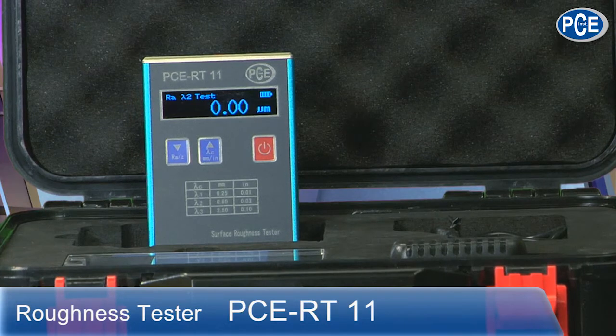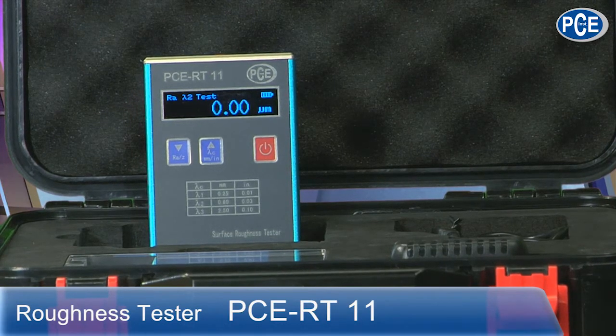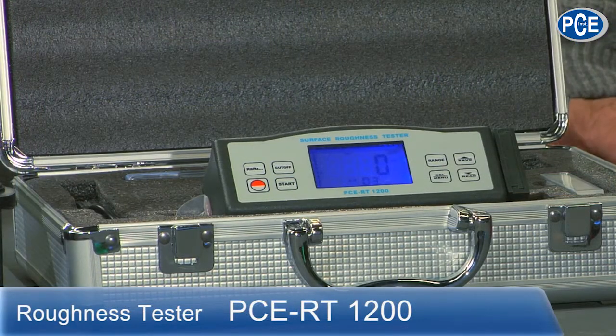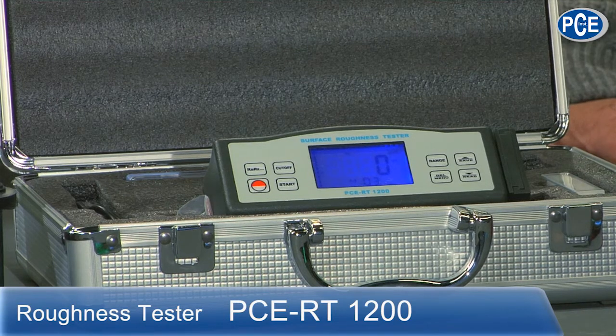I have built up in front of me three devices to measure technical roughness. First, the PCE-RT11, a device which is very handy, precise, and like all others comes in a case with power supply cable and connection cable, user manual and calibrating norm. A very practical device which you could maybe carry in your trouser pocket when you don't have anything else in them. The next device is the PCE-RT1200, a device which is also mobile with extreme high exactness in the area of 10 micrometer. It can show 1 nanometer.